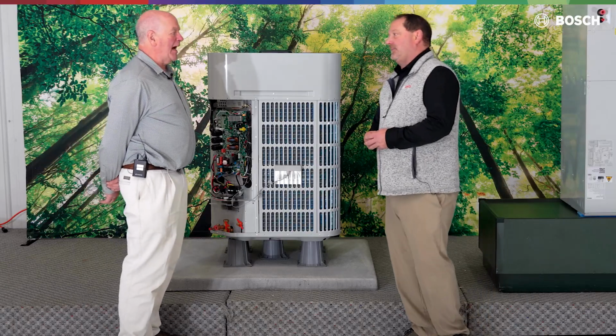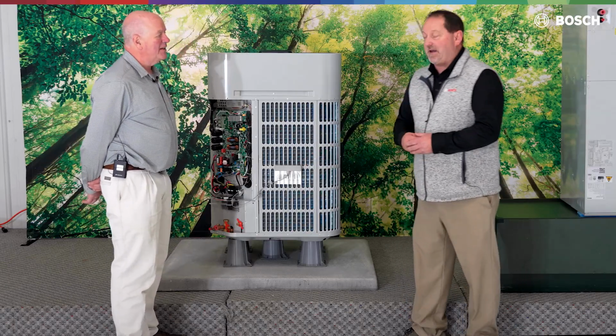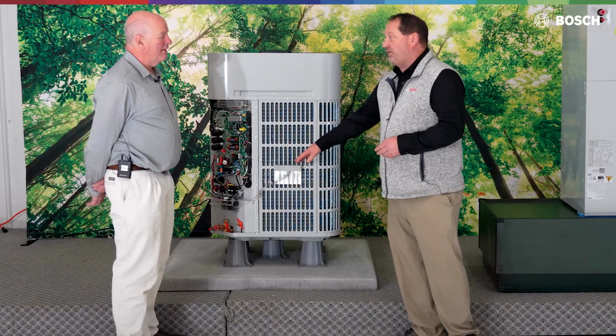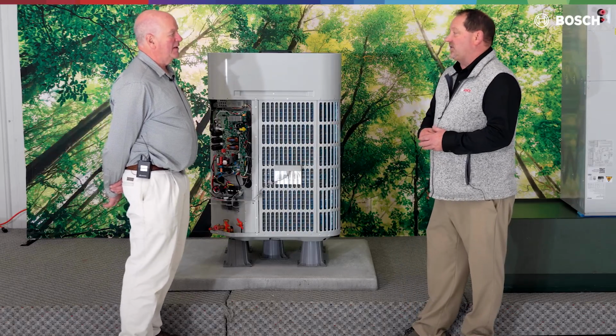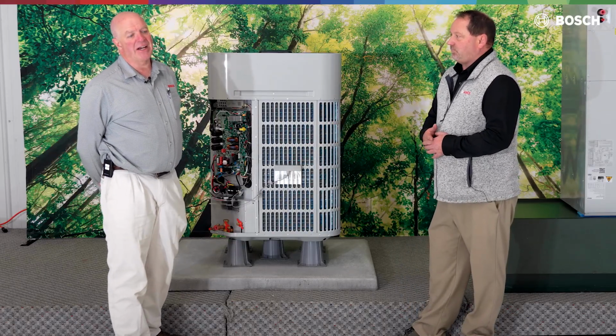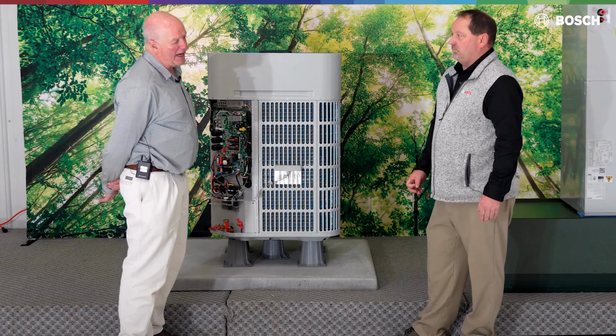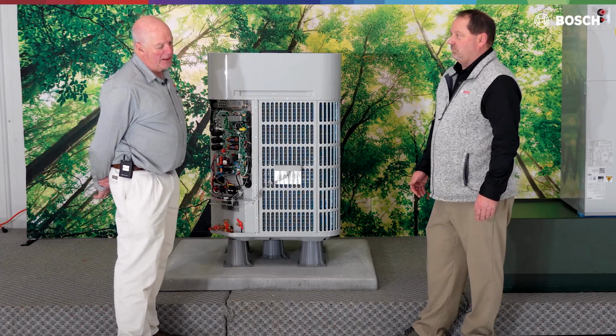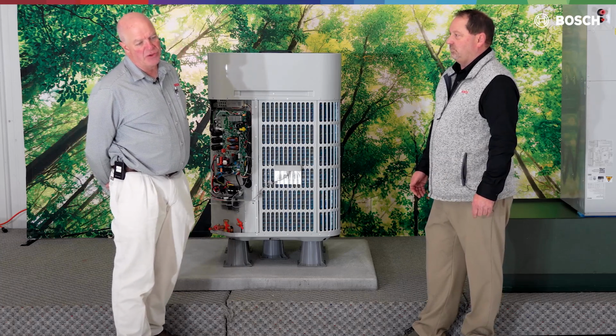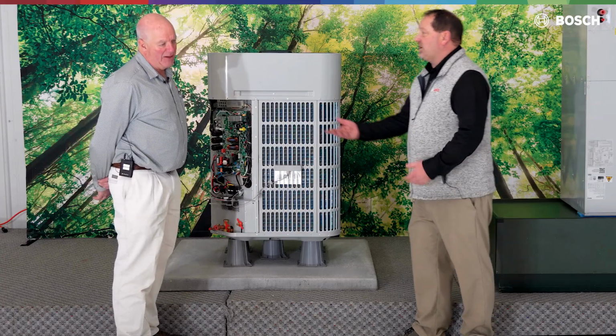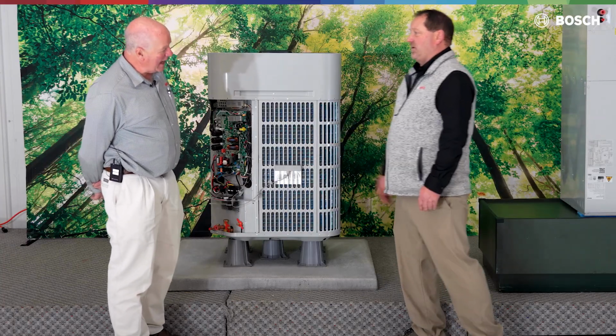And what's my suction line? My suction line in this case is a factory 7/8 service valve, again paired with the 3/8 liquid valve. So we can actually downsize our suction line one size. We can move down to 3/4. If you do a 3/4 suction line, you can lose up to 10% of your capacity. That was going to be my question. Are we going to lose capacity at that point? We can, depending on the length.